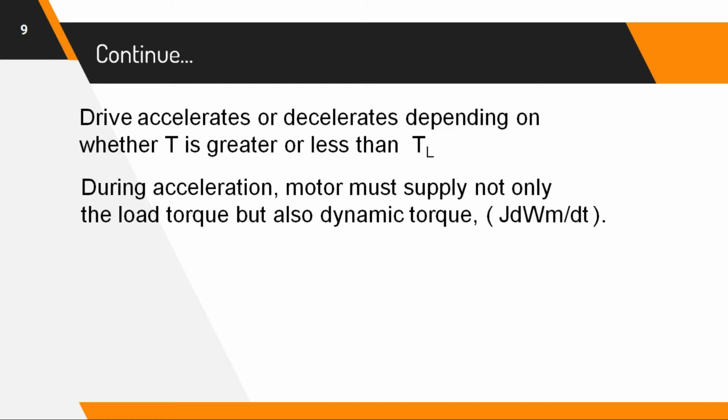A train, that is a traction load, is very heavy, so if you want to increase the speed, then the motor torque should be very high. If a fast transient response is required, then motor torque should be maintained at a high level, and the motor load system should be designed with the lowest possible inertia. If the inertia is low, the motor will of course respond quickly to transient operations.